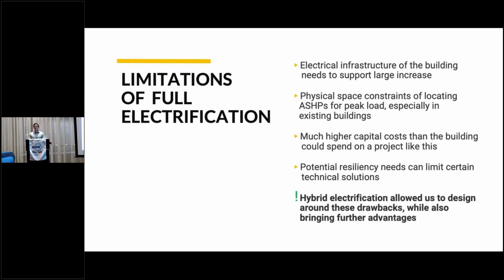Additionally, as your heat pump derates, and on that previous slide, it'll show up again, if you want to fully cover your electric load, even at your 15-degree design day, you have to install so much more capacity. In this scenario, it came out to we would have needed 3 times the capacity of air source heat pumps to fully cover the electric load.